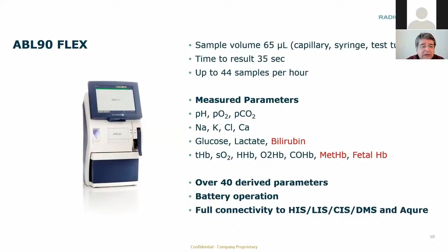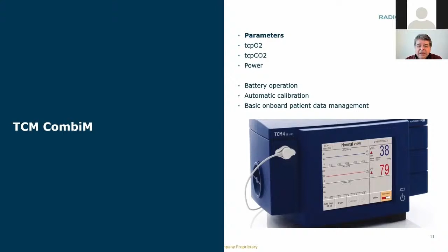TCM CombiM is the name of this particular model of transcutaneous monitor. It measures transcutaneous O2, transcutaneous CO2, and also power supplied to the electrode to keep temperature constant. Of course, the main parameters here are oxygen and carbon dioxide, but in some particular cases you can find power also a useful parameter. It calibrates automatically. Again, in case of patient transportation or power interruption, it automatically switches to battery, and it has basic onboard data management capabilities.